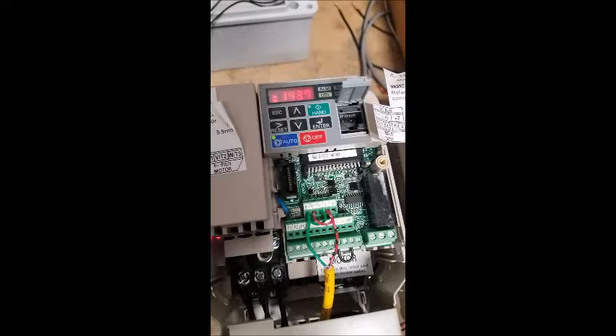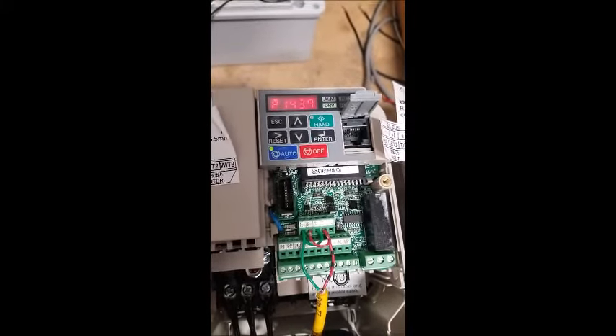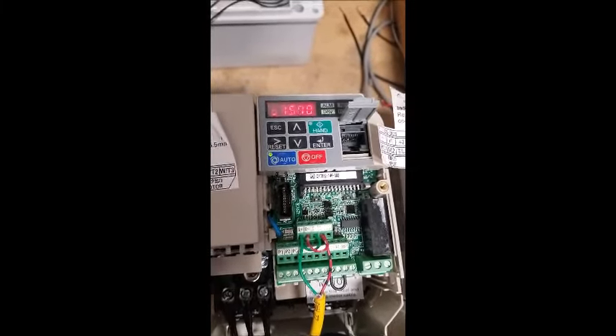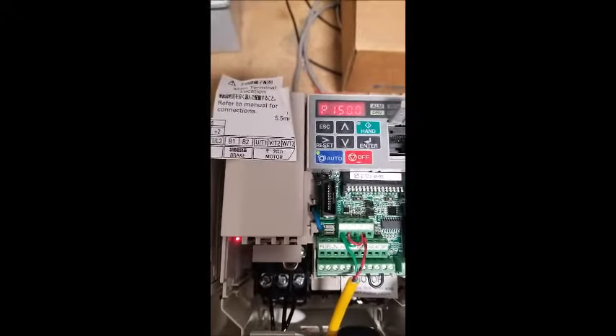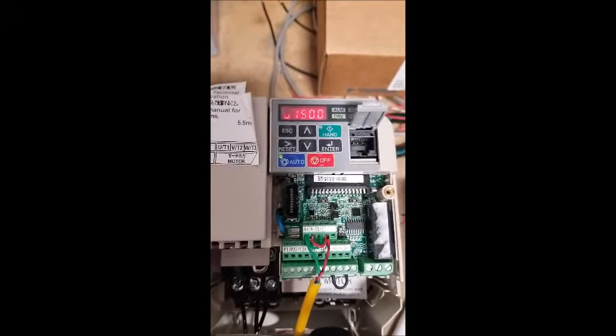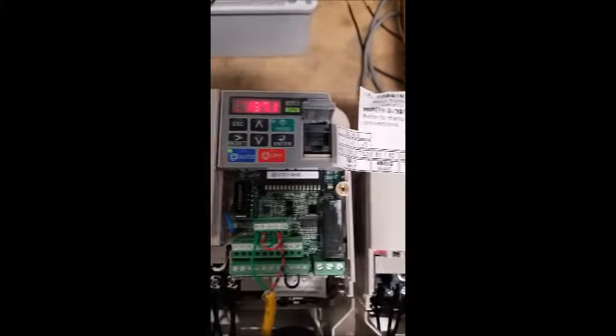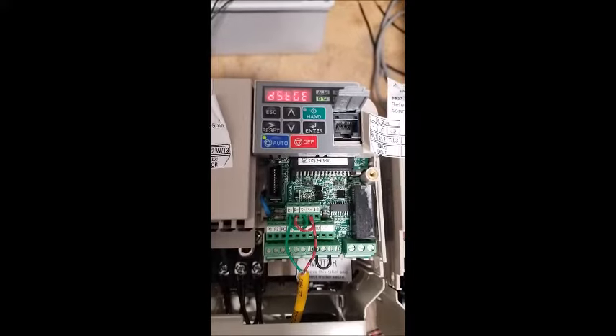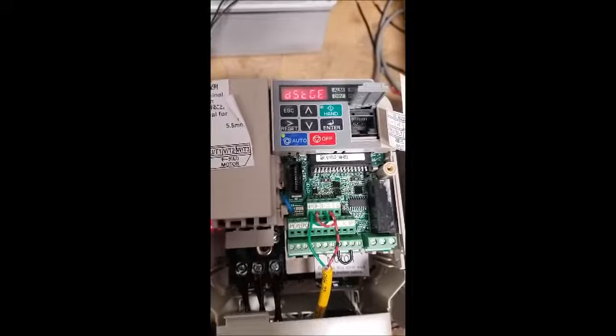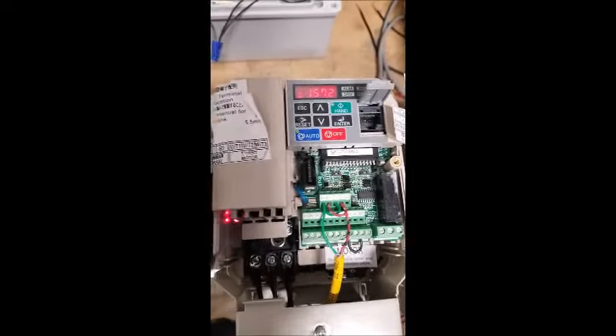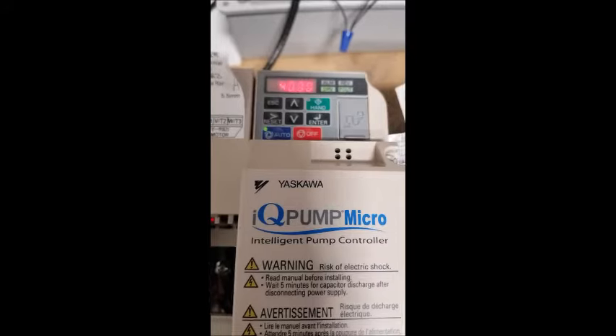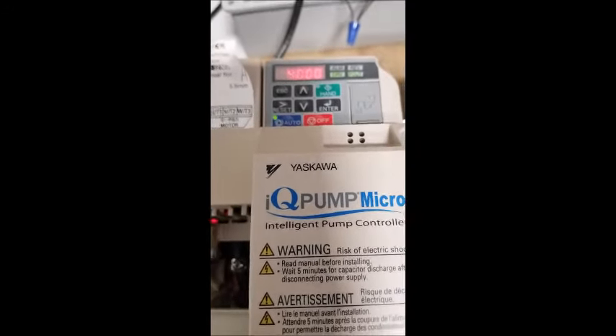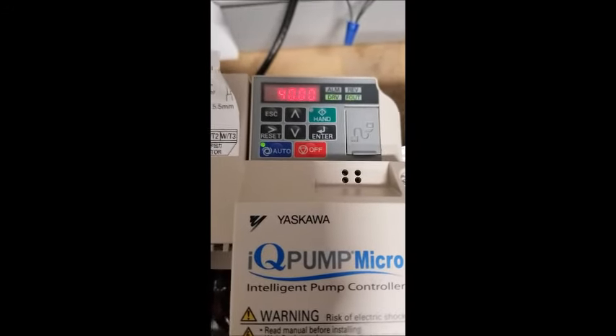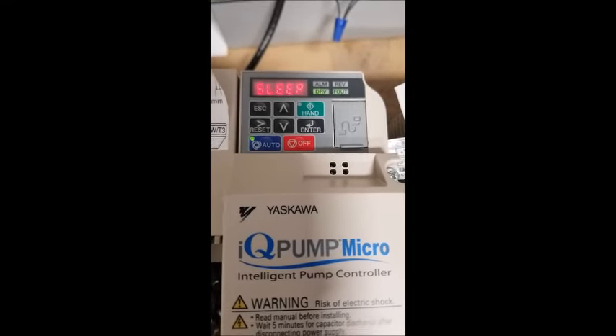And now, if the pressure were to start rising in the system and get above 150, you'll see the de-stage process begin. I'll pull this drive offline, de-stage this drive. After a delay time, this drive will go off. And then we'll go to the main drive, and it's being commanded by the pressure loop now to run at 40 Hertz, so after about 5 seconds of that, this drive will fall asleep.